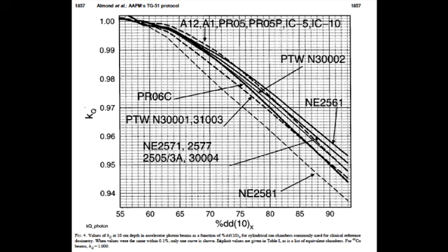So you remember from previous videos that the beams with a smaller percent depth dose are lower energy, they're softer, and higher percent depth dose are harder beams, like an 18 MV beam, let's say. And so that's the energy spectrum, or we could say the beam quality. So this is why it's a quality conversion factor.